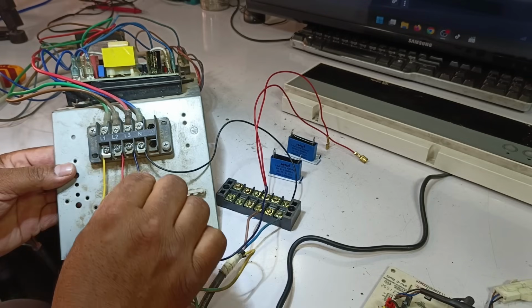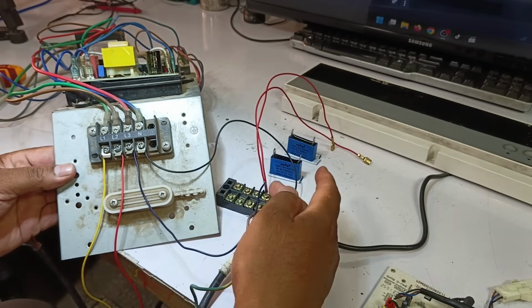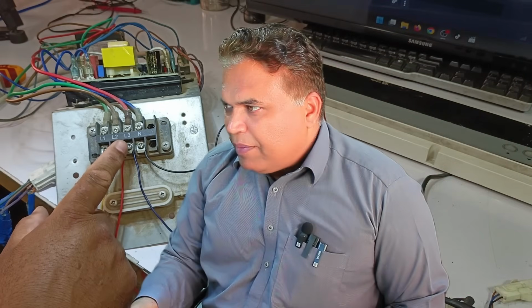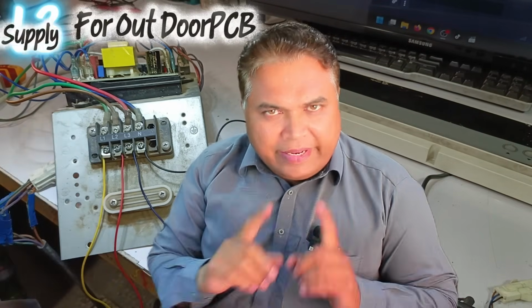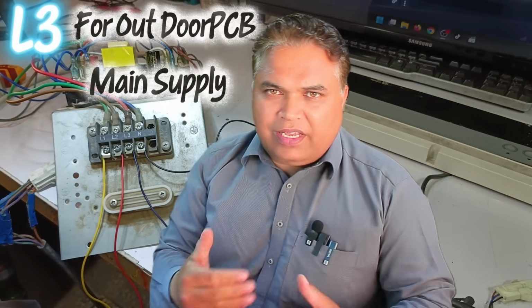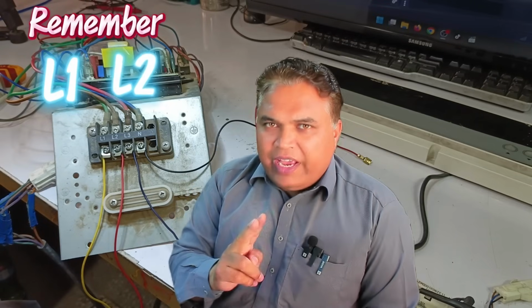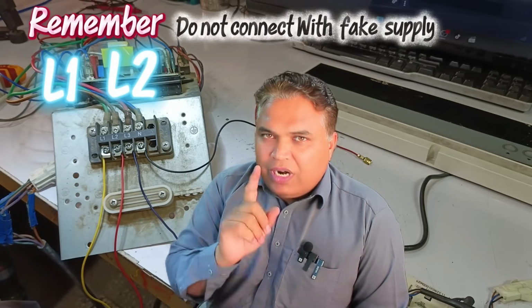We must provide it directly from the main single-phase supply, without involving any capacitors. As I explained earlier, the L3 line is the primary input that powers the outdoor PCB. It must be connected directly to the incoming single-phase supply. Meanwhile, the other two supplies, L1 and L2, are fake phases that we are creating using capacitors. These fake phases must not be connected to L3.